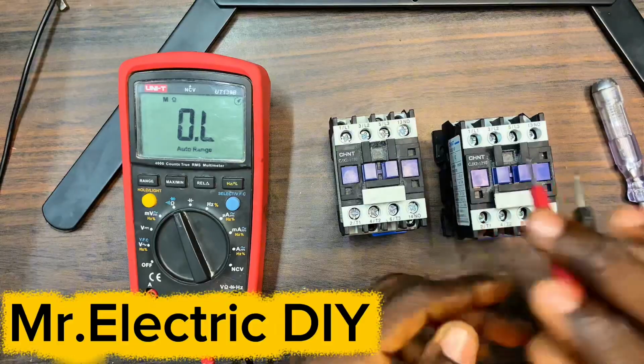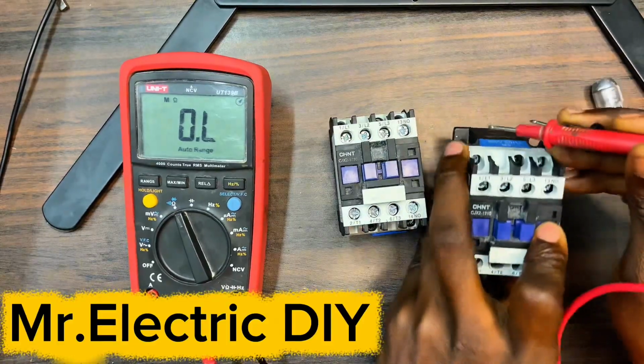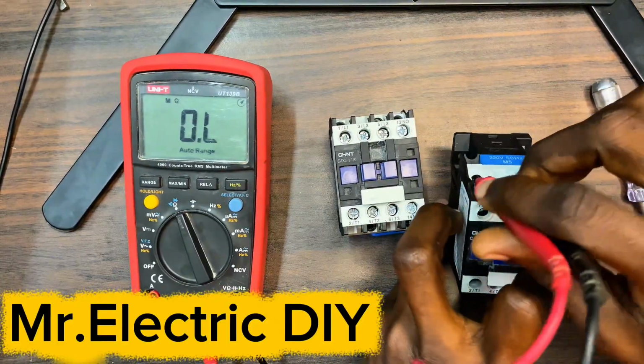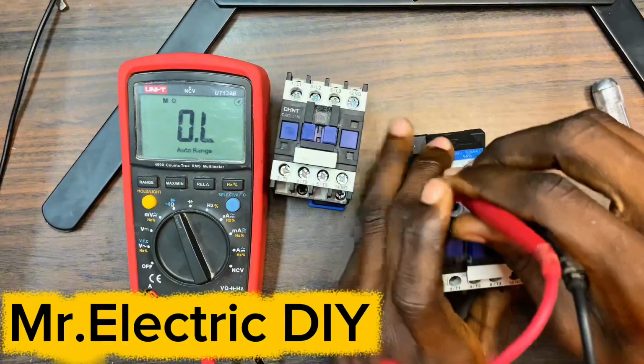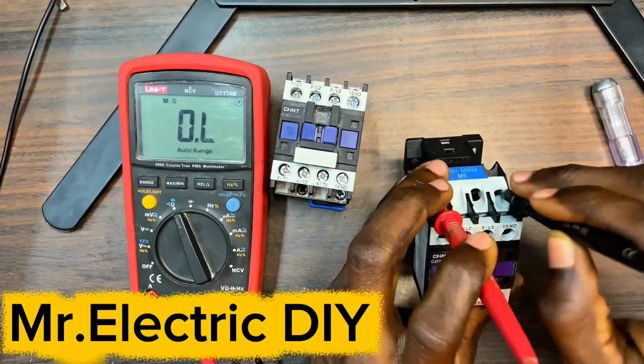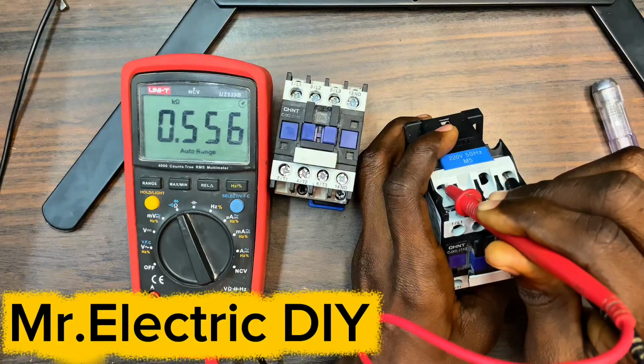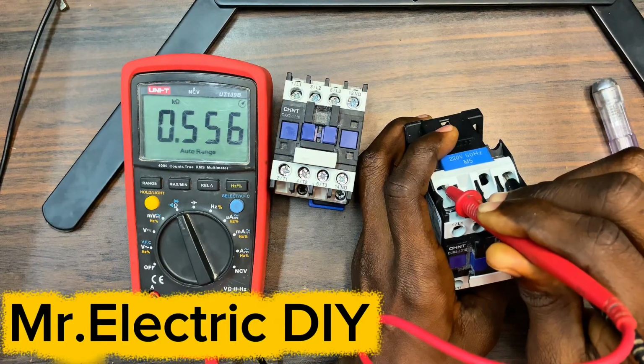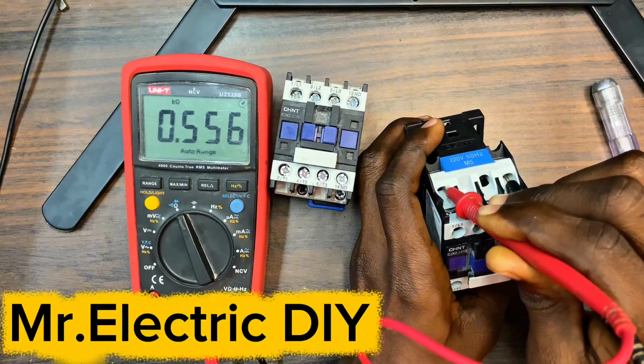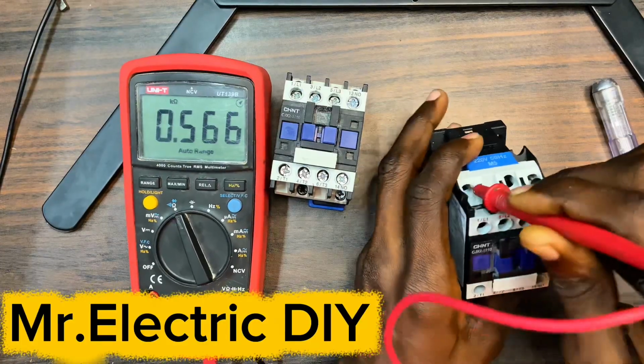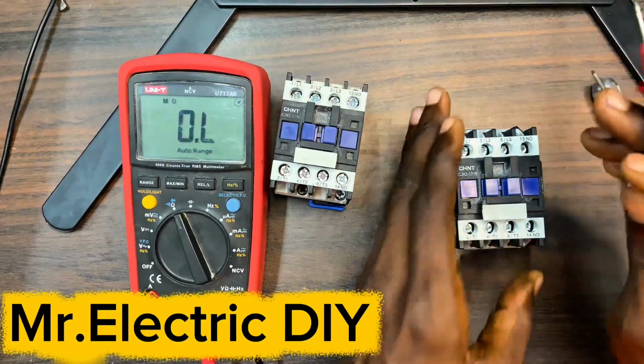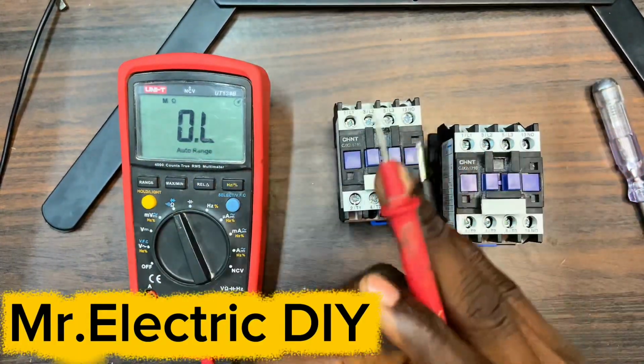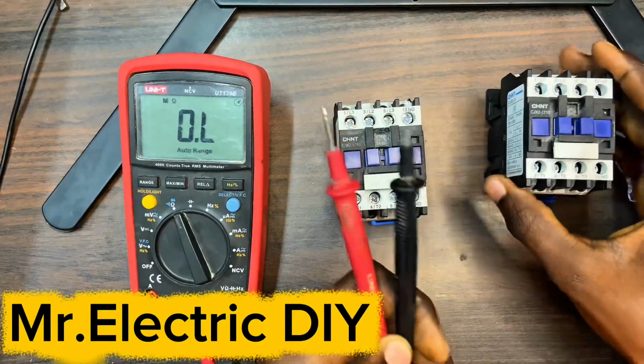So what I have to do is to connect the probes to this side. We have 0.556, that is 556 ohms. So I can tell that the coil in this magnetic contactor is in good condition. This is the first one that I checked. The coil is in good condition.